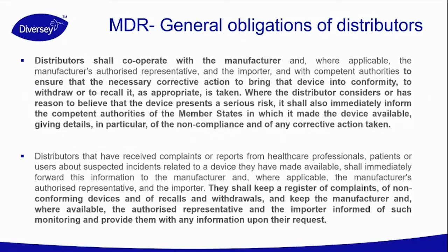Where the distributor considers or has reason to believe that the device presents a serious risk, it shall also immediately inform the competent authority of the member states in which it made the device available, giving details in particular about the non-compliance or any corrective action that has been taken.